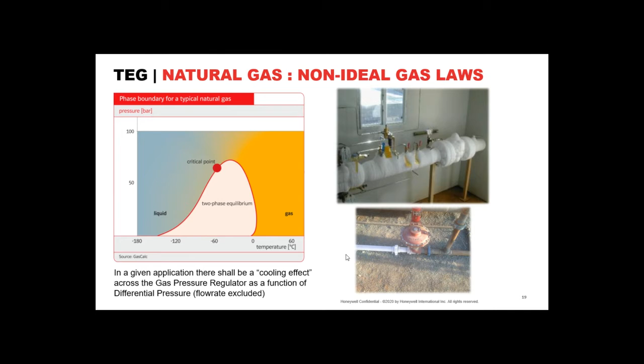Now then, if we drop the temperature, it's a very simple rule of thumb for a bar, a temperature drop. We can move into the world of TEGs, and we can then consider self-powering the vibration sensor. So it's good to have the vibration sensor, that's the predictive element, but you have to power it. Bear in mind from those early photographs, these things are quite isolated, never intended, for numerous decades, to be powered in any way. Any smart approach to active monitoring was pneumatic. So to have this thing self-powering would be absolutely awesome, and the TEG's obviously the most viable way to go.